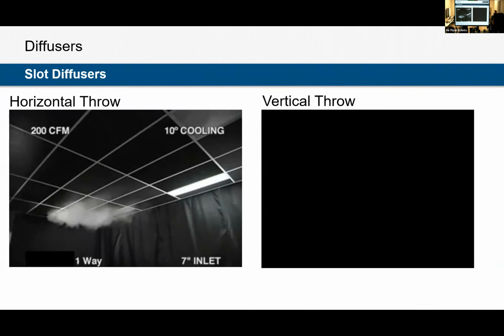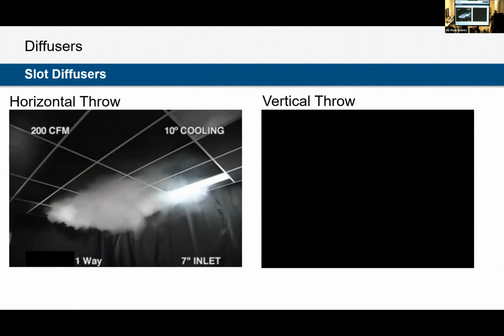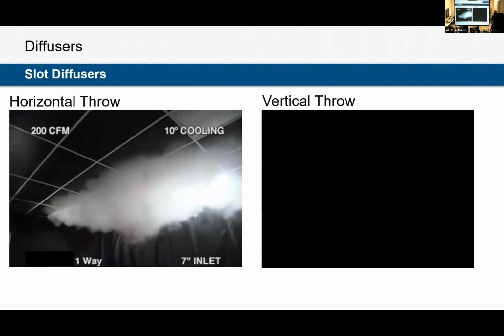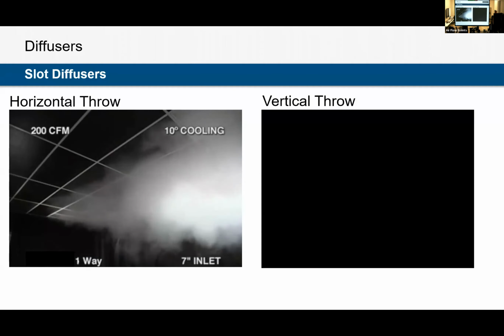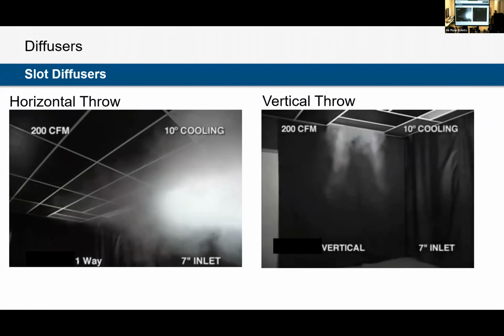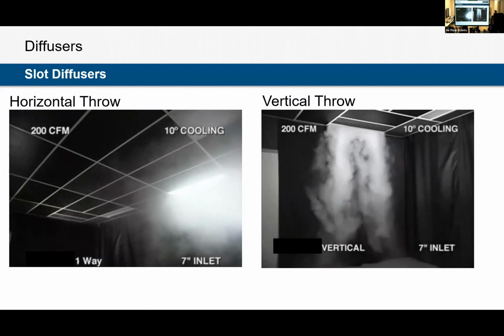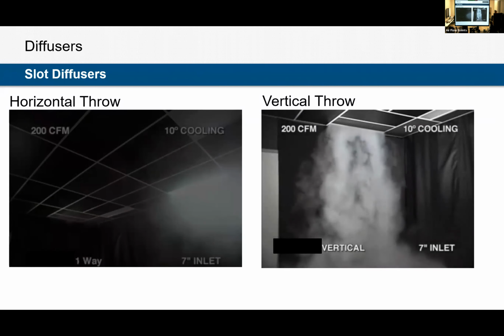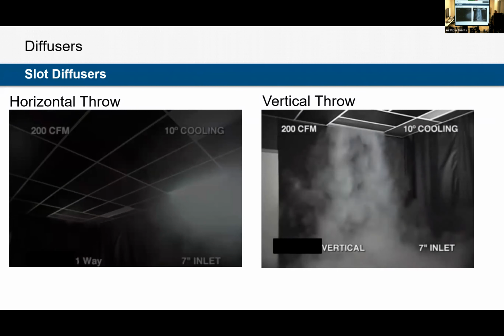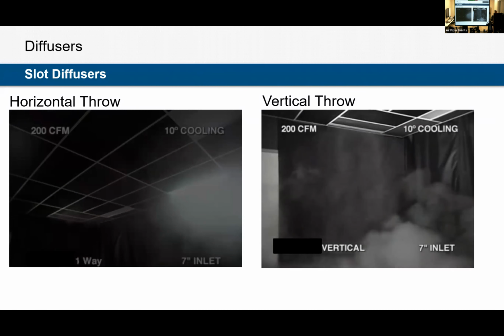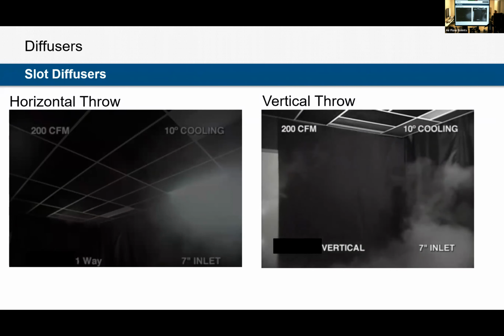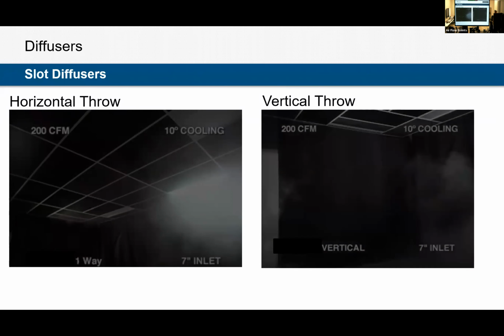Smoke video of the slot diffuser. The one here on the left is our horizontal throw across the ceiling. They do travel pretty far. Slot diffusers have a pretty long throw because they are coming out in one direction. And then your vertical throw. This would be an example of washing the window. You can design that throw to come down pretty straight and vertical like a rectangle, or you could use some angled baffles or an angled plenum on it and have an A-frame shape come out of the diffuser. So a couple of different ways to wash the window.